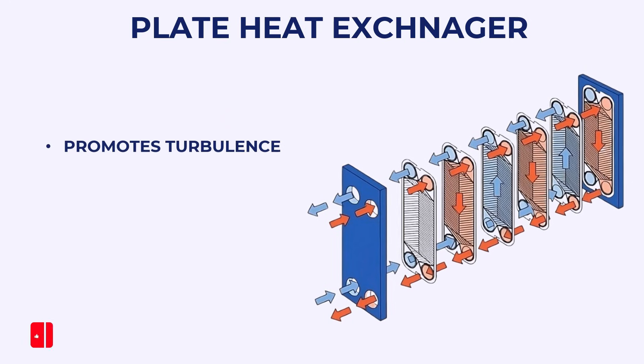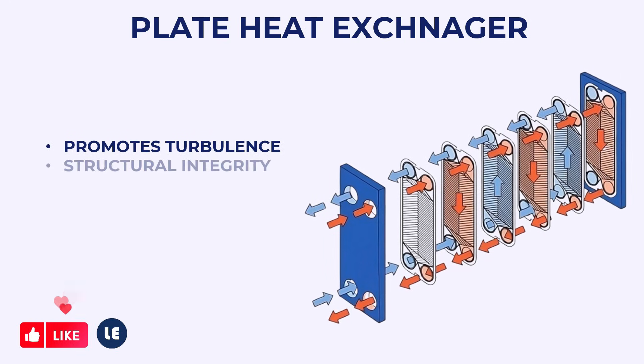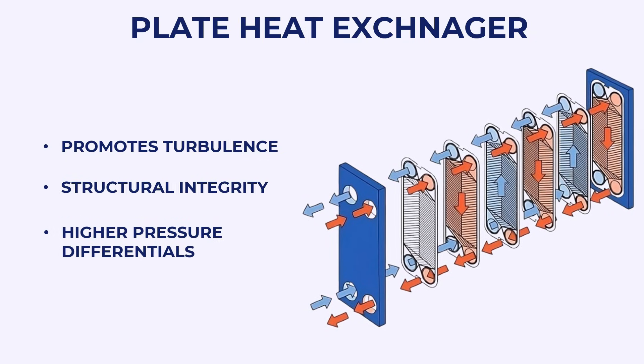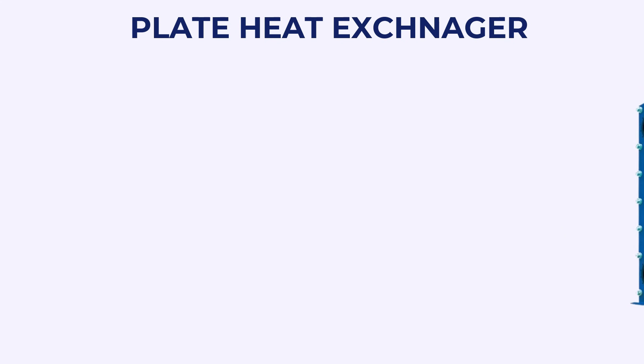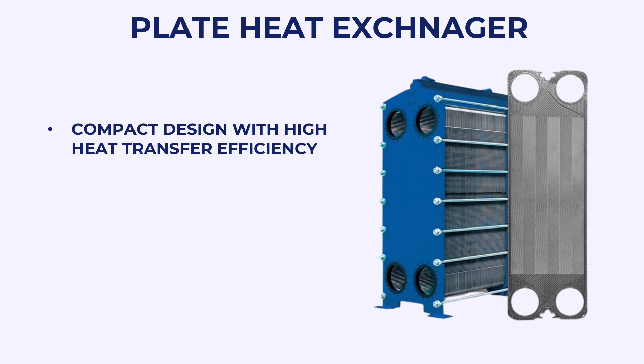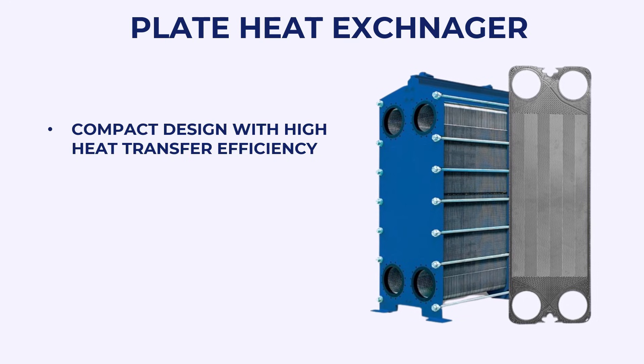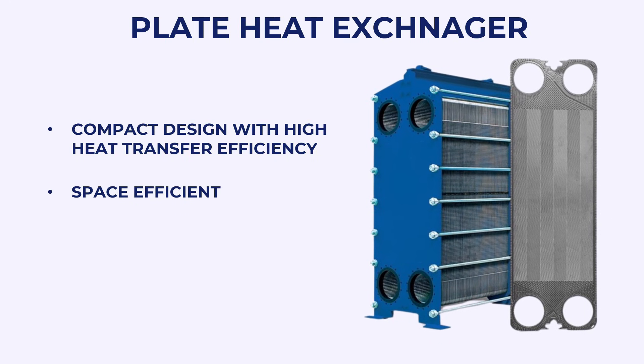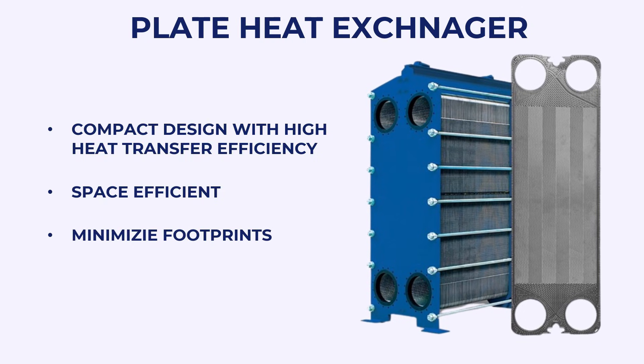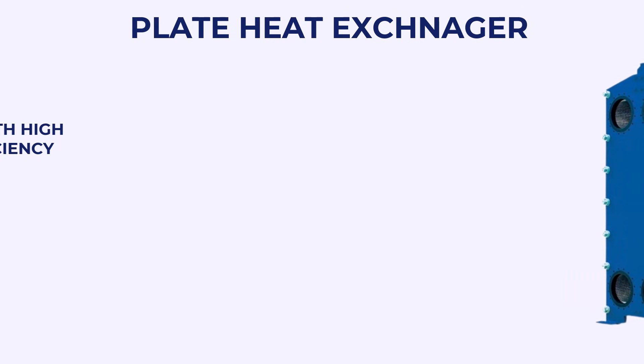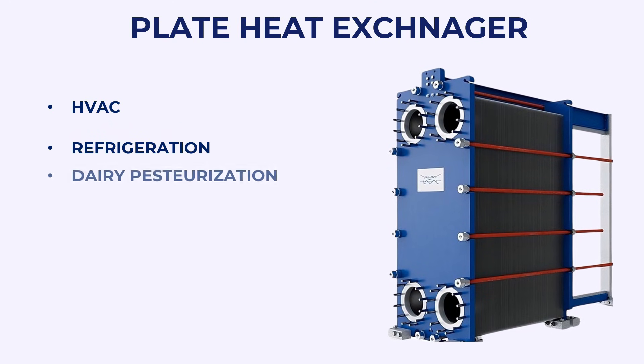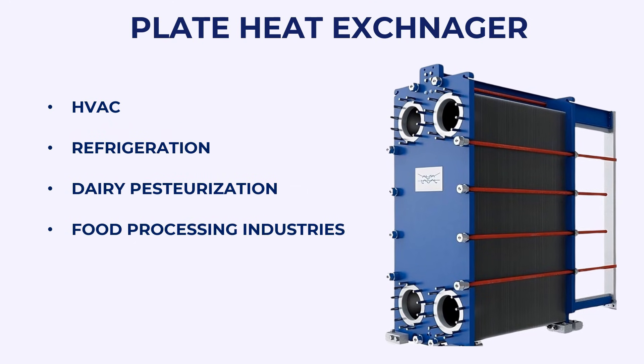The corrugated design not only promotes turbulence, but also helps to maintain structural integrity, allowing for higher pressure differentials between the fluids. Plate heat exchangers have a compact design with high heat transfer efficiency, making them space efficient and well suited for applications where minimizing footprint is crucial. They are widely used in HVAC, refrigeration, dairy pasteurization, and food processing industries.